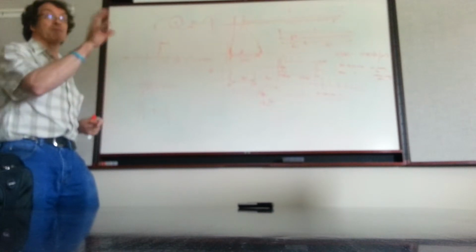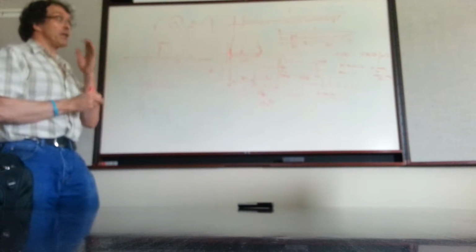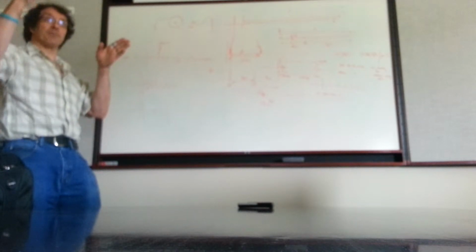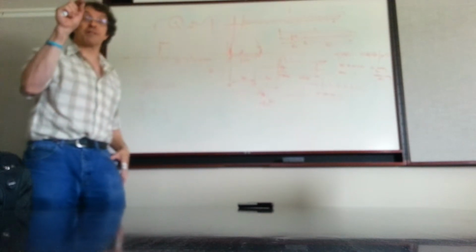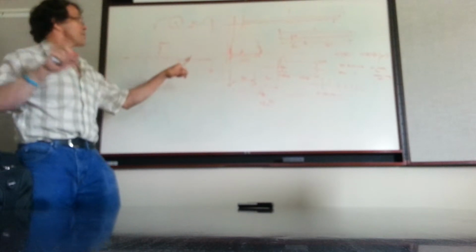Quick PDSL is a lot faster, and you can do it from the same screen that you use in PD. The other downside with the quick PDSL is that when you set length, you need to see the pulse from the front and the pulse from the tail. So you need to see these two guys here. Then there's a button where you type in the feet length and it says cal for length. So it'll set the distance between these two on your screen as being 1,200 feet, whatever.